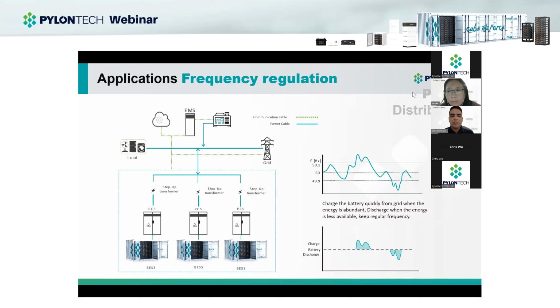In this solution, we can also aggregate a generator like we have here in the diagram. This can be a second option in case the batteries are completely discharged and we still have issues with the grid. In that case, the EMS can tell the generator to discharge, also to maintain the frequency.